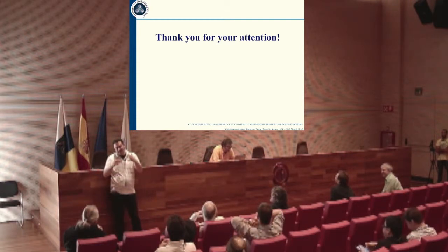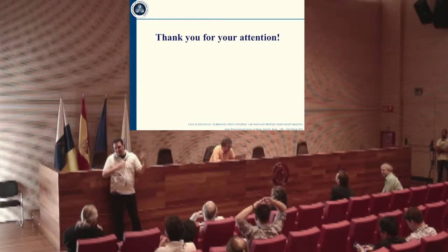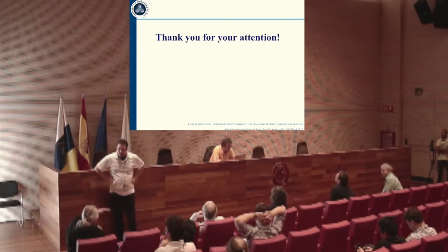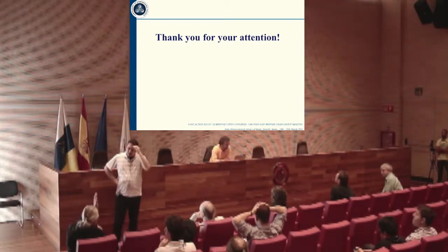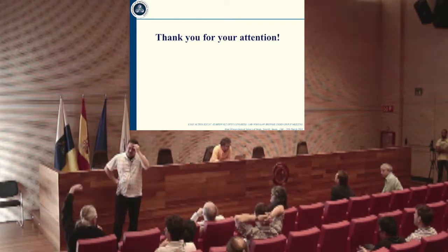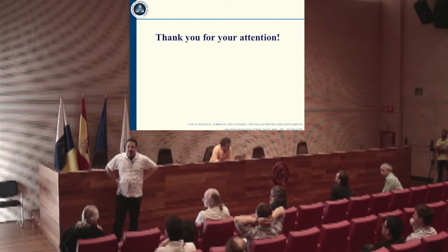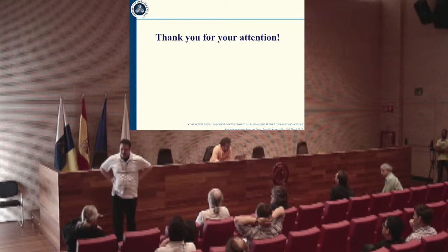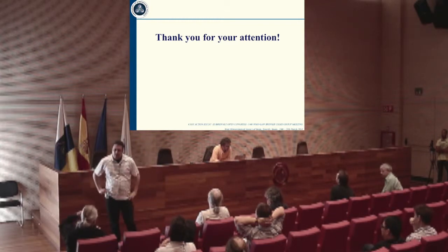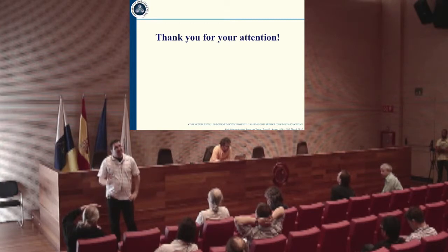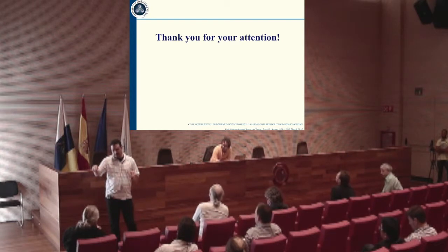You mean about the wavelength accuracy, where you were doing the mercury lamp test at different angles of the prism? Okay, this one, through the quartz window. And then you did it through the diffuser. Which one was the odd curve? Well, several of them were pretty much on top of each other, and one of them was displaced. I think that was for the horizontal position of the quartz window. The step was displaced.